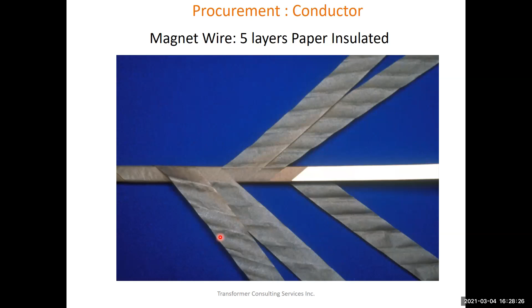Besides that, when the manufacturer will give us the insulation, this paper insulation, there can be different type of paper insulation. Here you see 1, 2, 3, 4, 5, 6, 7. There's 7 type of paper, crepe paper, kraft paper. What type of paper the manufacturer will give to you and how much insulation the manufacturer will give to you, it depends on what is the manufacturer's design philosophy. Whether the manufacturer is taking 50 kV per millimeter for the breakdown voltage or 40 kV per millimeter for the breakdown voltage, that kind of gives an idea about the manufacturer being aggressive into design or conservative into design. If the manufacturer is aggressive into design, in that case, those compromise of the quality during the manufacturing process can cost the reliability and the life of your transformer.